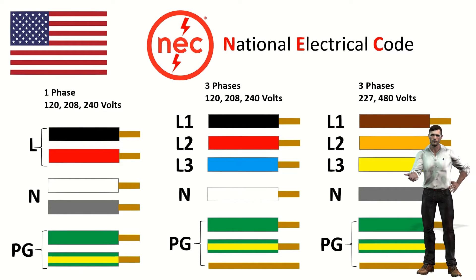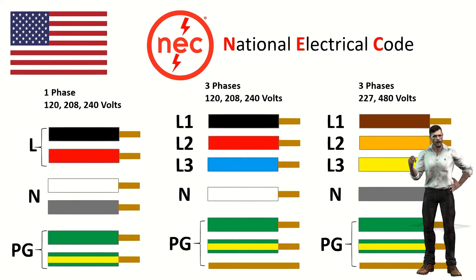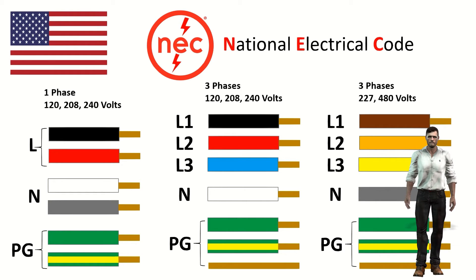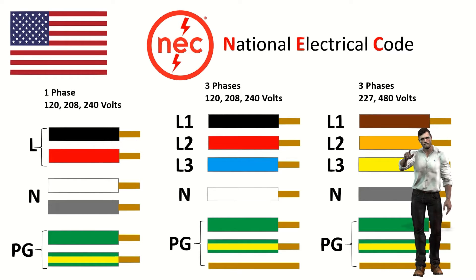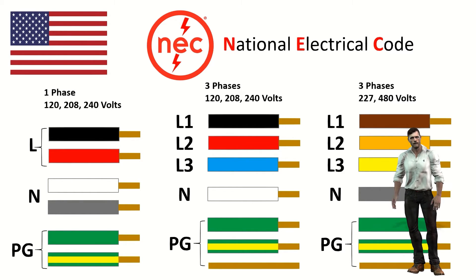For three-phase installations of 120, 208 or 240 volts, also used in the residential and office environment, the following colors are normally used: black for line 1 (L1), red for line 2 (L2), blue for line 3 (L3), and white for the neutral (N). For the protection cable or ground cable we have the color green, green with a yellow stripe, or the bare wire.